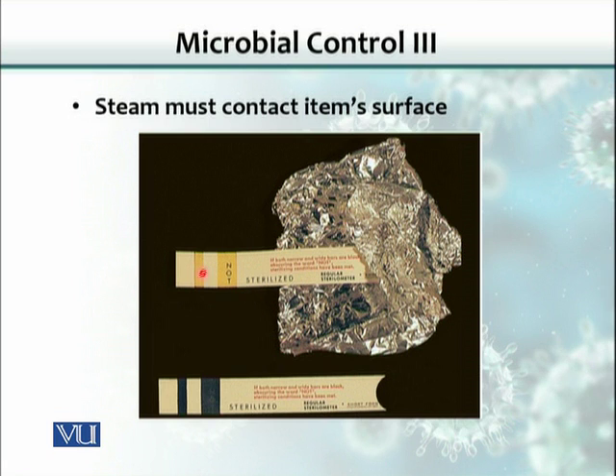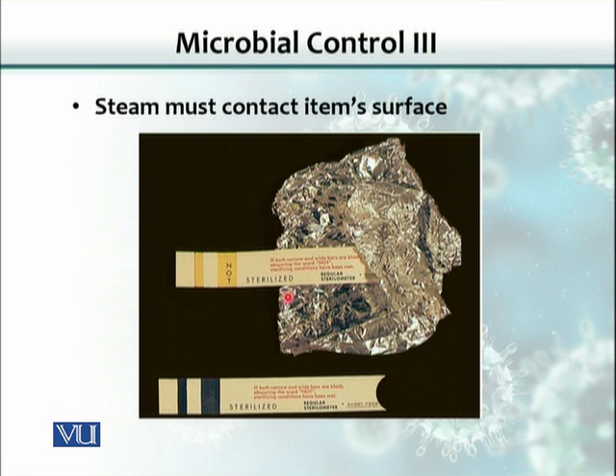There is also autoclave tape — a strip with words or lines engraved on it that are normally not visible. When the tape undergoes the required pressure and temperature of 121 degrees Celsius, those lines appear. This is used to monitor the sterilization process: if you don't see the change in the tape, the required temperature was not achieved and sterilization was not completed.